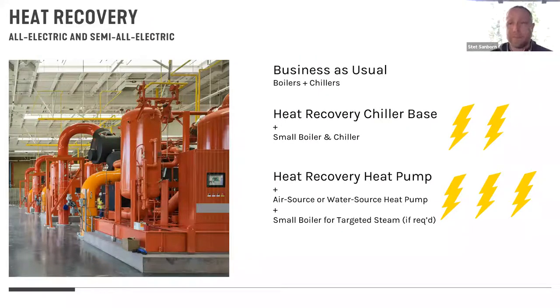The top one is more of a business as usual case. They're using boilers, chillers, cooling towers, very state of today. You might use really good design, still around mild supply water temperatures where you can, only doing deep temperature chilled water, like 42 to 44 degrees, if you actually need to do dehumidification. We're lucky enough that we don't in Northern California, which I know, growing up in the Midwest, that's not true for everybody.